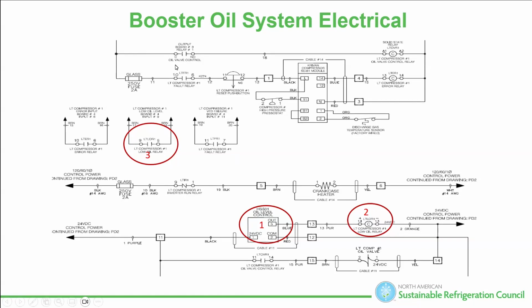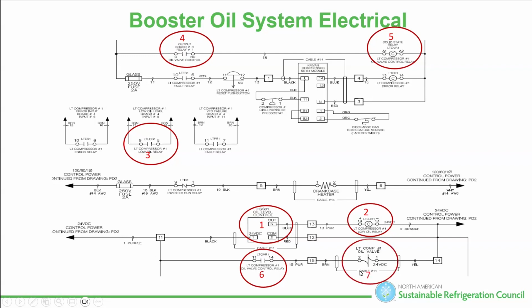The controller says, all right, well, how about this oil valve control? All right, that's pretty simple. I close that board endpoint. When I close that board endpoint, it energizes LTOVR1. When that energizes, well, we already determined there has to be a coil or a relay pin somewhere, a normally open or normally closed set of contacts somewhere. And so let's start looking for LTOVR1. Here we go. Pin 6. Close that. Oh my God, can't believe it. We finally turned the solenoid on to energize the oil. Any break in this circuit was going to cause an oil failure, a mechanical issue. My compressor's off on oil.